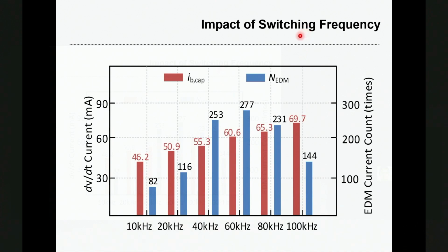And then we see the impact of switching frequency. With switching frequency rising from 10 kilohertz to 100 kilohertz, as you can see, the dV/dt type of current will increase due to the oscillations in the bearing current. But the EDM-based current will increase first and then go down a bit. It increases first because with high switching frequency, there will be more high voltage chances, which will trigger more EDM events. But with the switching frequency going even higher, the duration of the high voltage at each pulse will be smaller. Then it will not trigger the EDM events. That's why the number has reduced.